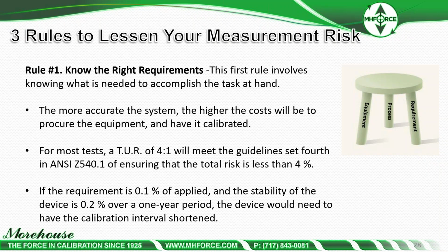For most tests, a TUR of 4:1 will meet the guidelines set forth in ANSI Z540.1 of ensuring the total risk is less than 4%. That's true. If the requirement is 0.1% of applied and the stability of the device is 0.2% over a 1-year period, the device would need to have the calibration interval shortened. That one is simple. Lots of people do this. Hey, I have a device that I want the accuracy to be 0.1% of applied. Then it comes in for cal and it shows that it's been out, and it's out by more than 0.2% over the year. The customer says adjust it. We adjust it, and they go on using it as 0.1. That's not the case. Here's a case where you really want to look at stability.